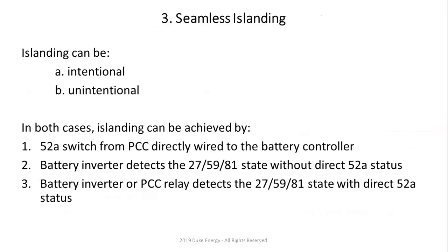All right. Third section is seamless islanding. So our particular system over here at Mount Holly has seamless islanding. Islanding can be either intentional, when you go to the island as a function of some kind of operating parameter, or unintentional, when you have a fault. Seamless islanding has to work for both, but you also have to make sure that you don't trip for some transients or some temporary faults on the system.